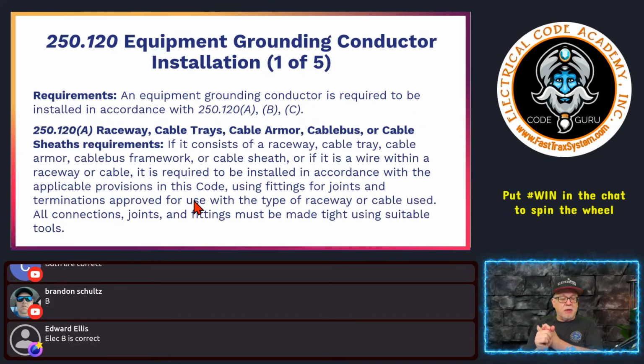So this is firstly saying, look, raceways, if they qualify under 250.118, and cable trays, unless they qualify, have to have a wire type equipment grounding conductor. It could be the raceway, it could be the cable tray as a supporting component, okay? Could be the cable armor in some things like AC cables, okay? But with MC cables, the armor cannot be used, so that will have a wire type inside of it. But basically what this is saying is if you're using these types of things as an equipment ground, then you have to make sure that you're using proper joining, proper connections, listed fittings that are listed for the application of grounding and bonding. All of that has to be met in order to establish an equipment grounding conductor with those types of options, okay?